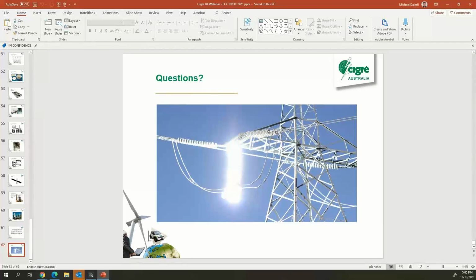I think for the pole 2, the electrically triggered, the voltage is not that high. I'm pretty sure it's less than 100 volts. I couldn't tell you the exact value, but I could definitely find out if I needed to. But there is an issue with the pole 2 system, and that is you need auxiliary power to provide power for that firing pulse, and that's derived usually from the voltage over the converter. So sometimes you can run into problems if the voltage goes nasty over the converter that you might not have enough to send a pulse. But our valve's designed really good. We haven't had any problems with that, but it is one issue with the electrically triggered design.